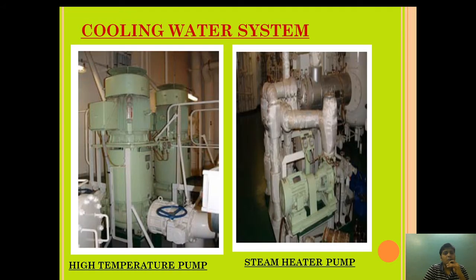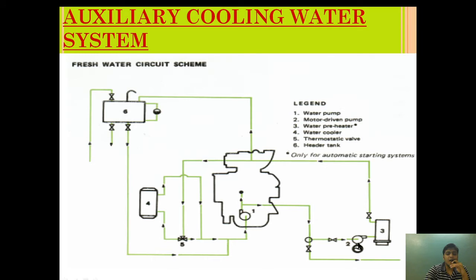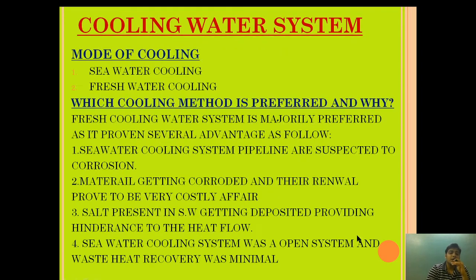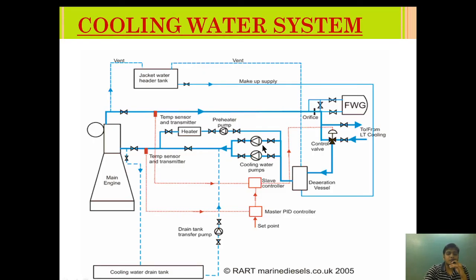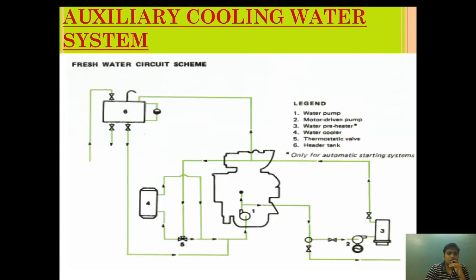Now let's look at the components of the cooling water system. The high temperature pump and the steam heater pump are both provided. As shown in the diagram, in normal operating conditions the HT pump raises system pressure to around 4 to 5 bar. When the engine is stopped, the preheater pump runs and maintains the pressure at around 4 to 5 bar in the system.